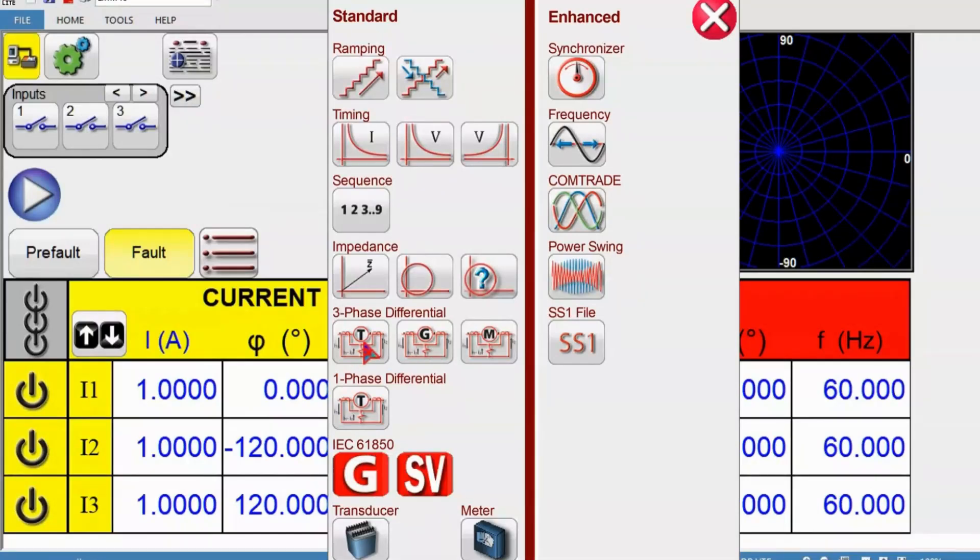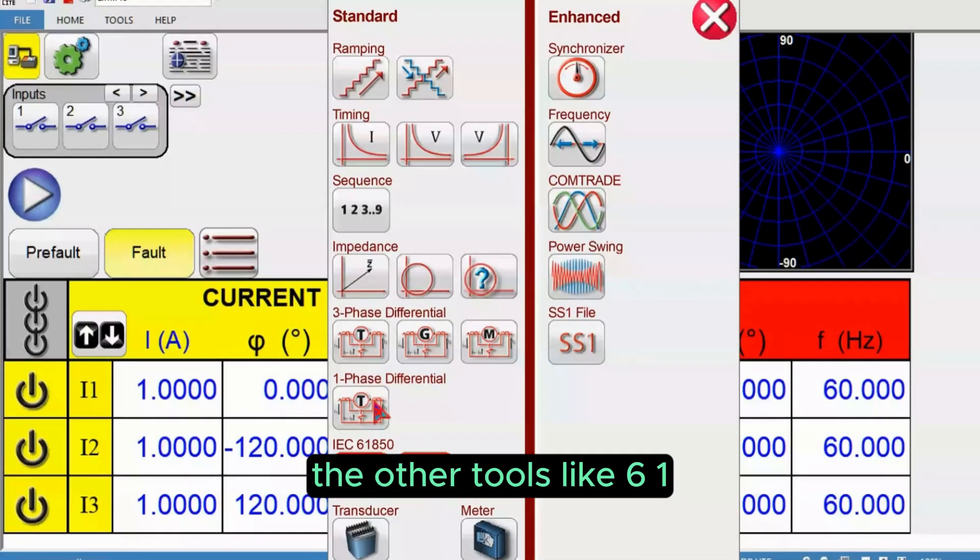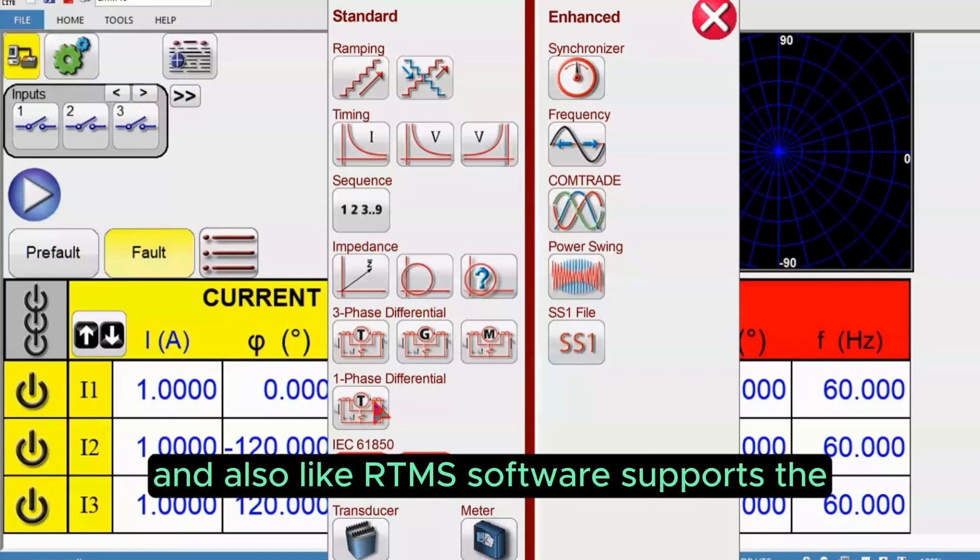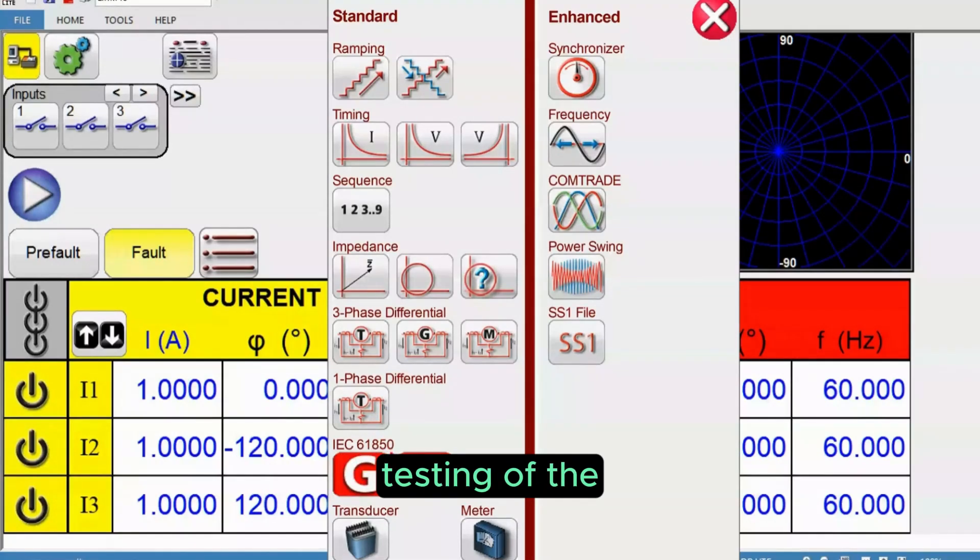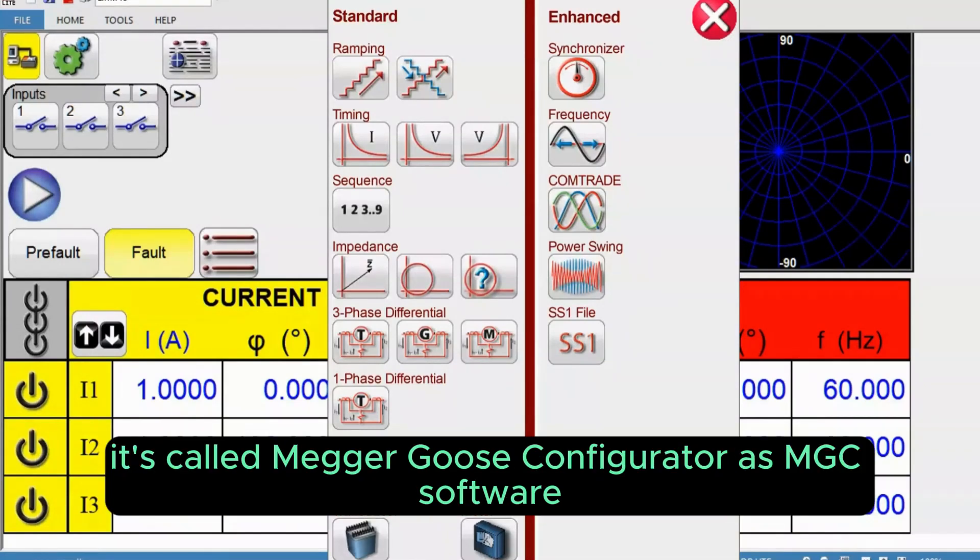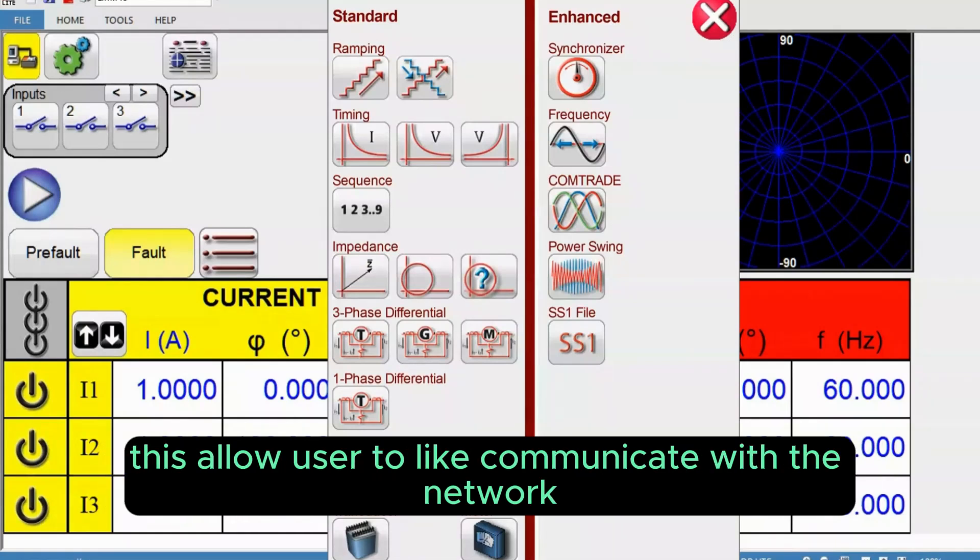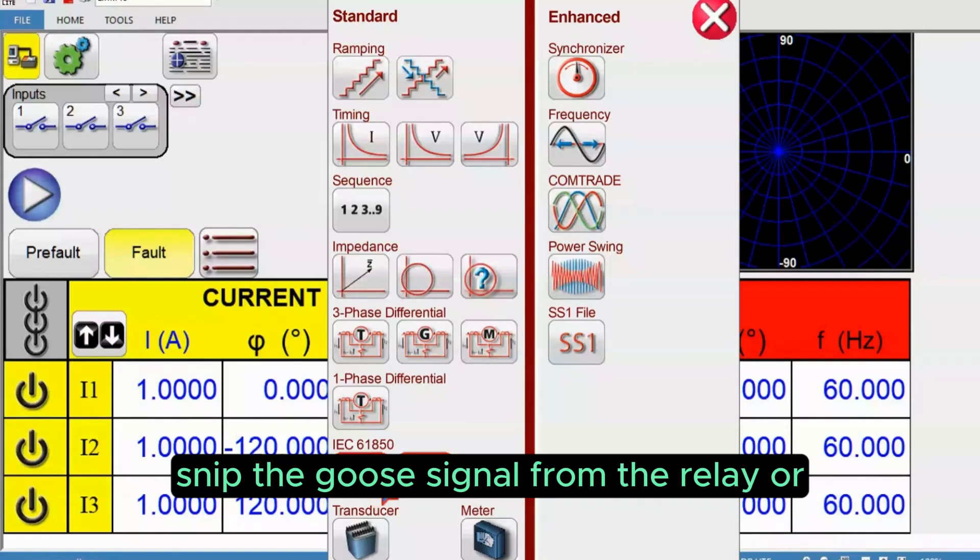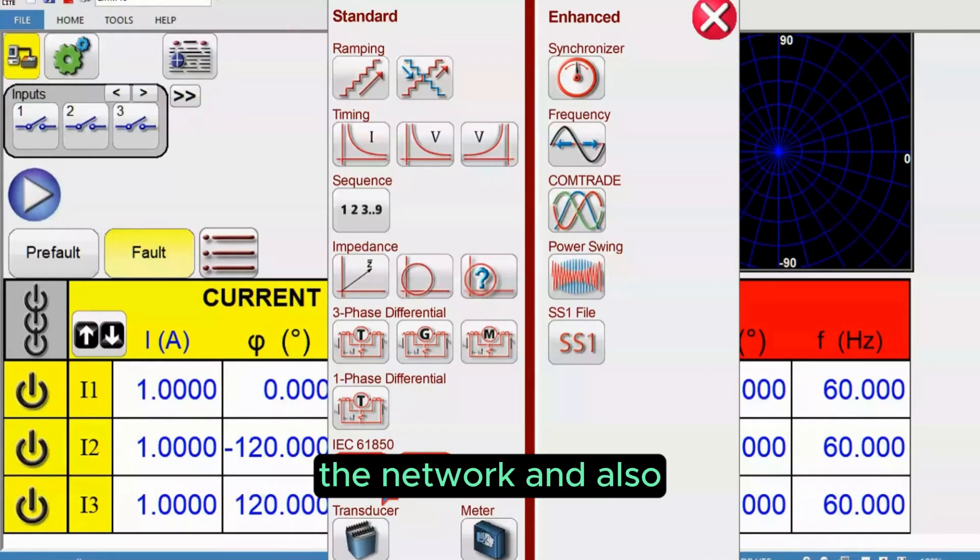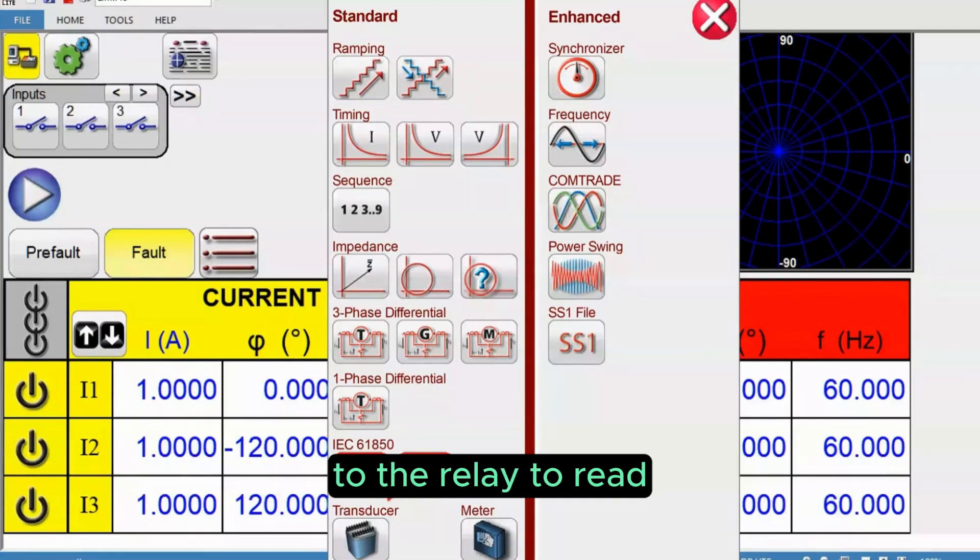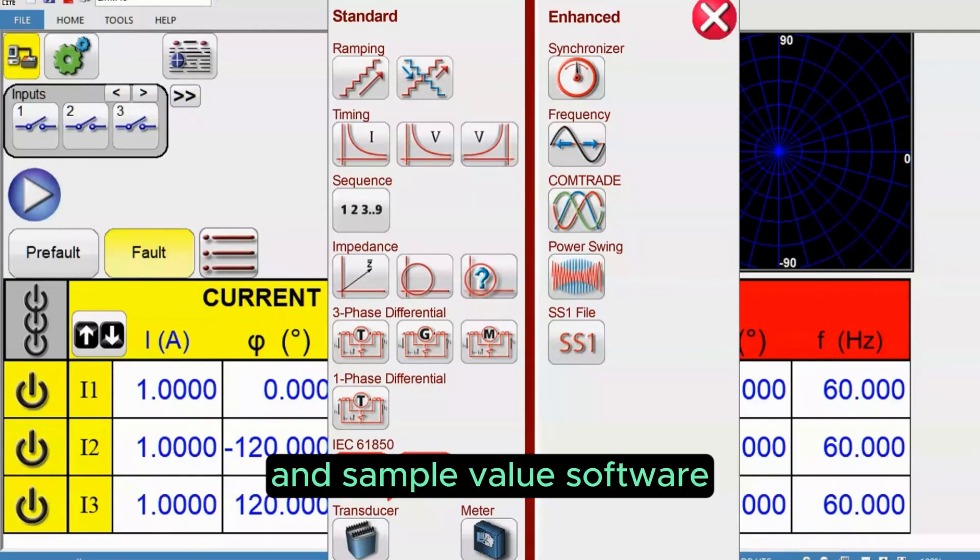The other tools like 61850 tools. The SMRT test set and RTMS software support testing of IEC 61850 technologies like this one, MGC, called Megger Goose Configurator. This allows users to communicate with the network or relay, snip the GOOSE signal from the relay or network, and also has the ability to replace the GOOSE signal into the network or relay.